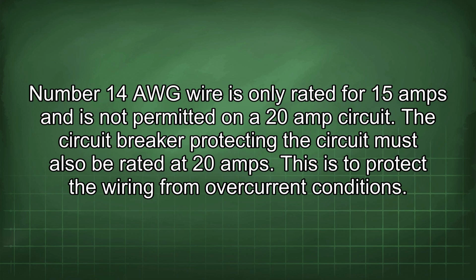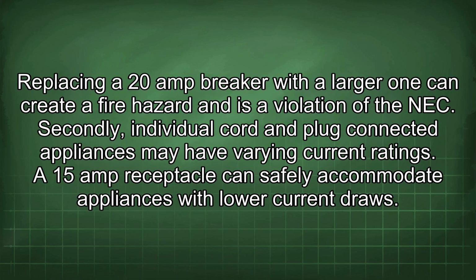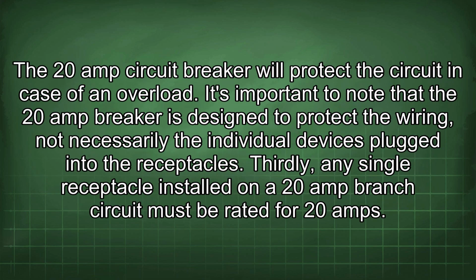The circuit breaker protecting the circuit must also be rated at 20 amps. This is to protect the wiring from overcurrent conditions. Replacing a 20 amp breaker with a larger one can create a fire hazard and is a violation of the NEC. Secondly, individual cord and plug connected appliances may have varying current ratings. A 15 amp receptacle can safely accommodate appliances with lower current draws. The 20 amp circuit breaker will protect the circuit in case of an overload.